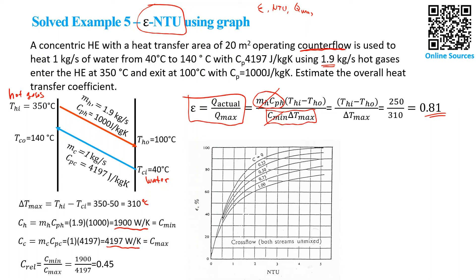We need to find NTU from the graph using the effectiveness factor and C relative. We find epsilon equal to 0.81 and C relative equal to 0.45. With these two coordinates, we find the crossing point. This line is for C equal to 0.25 and this one is for C relative equal to 0.5. It will be slightly above this line. The epsilon is 81%, so we take the straight line and find the crossing point, and we find NTU equal to 2.9.